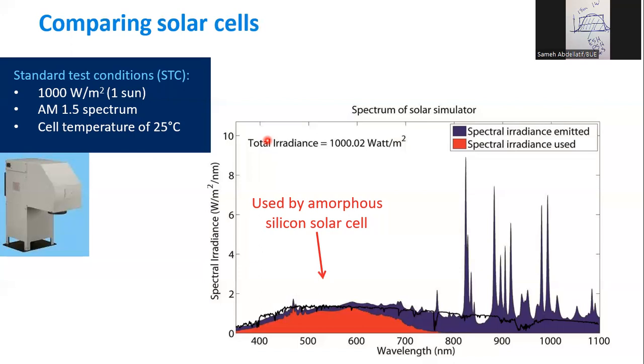Solar simulators are characterized based on three factors. Actually, what's called the temporal stability, or the stability of the light source against time, what's called the uniformity, which means within the targeted area, to what extent light is uniform, and what's called the spectral mismatching. So you can hear about what's called the AAA solar simulator. That means that this solar simulator is classified as an A class in terms of temporal stability, uniformity, as well as the mismatching with the solar spectrum, minimum mismatching, of course. And this is the solar simulator.